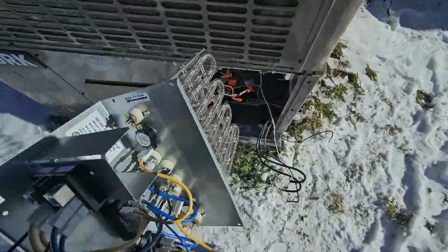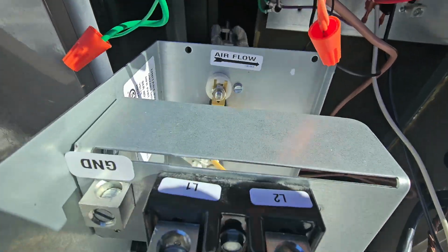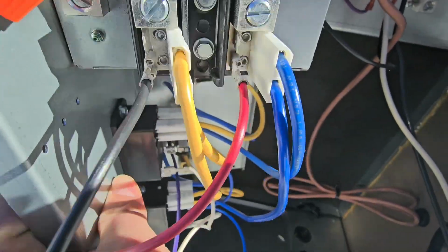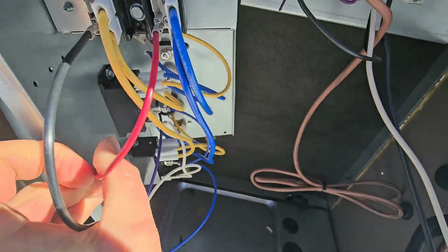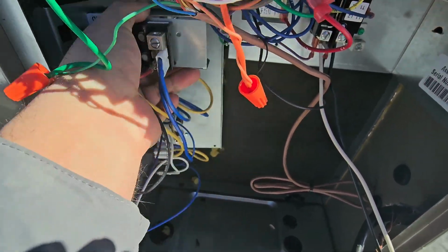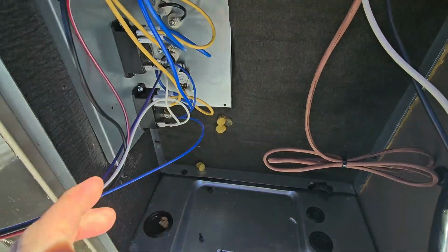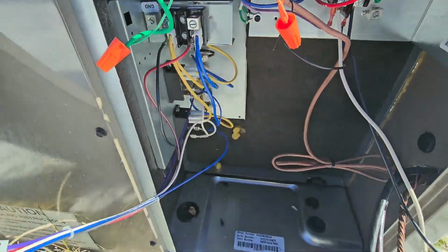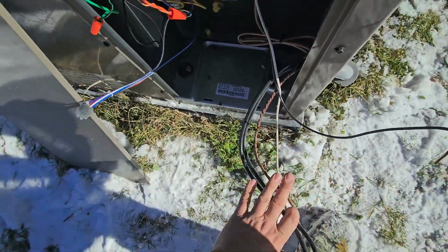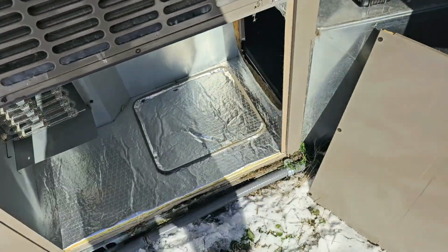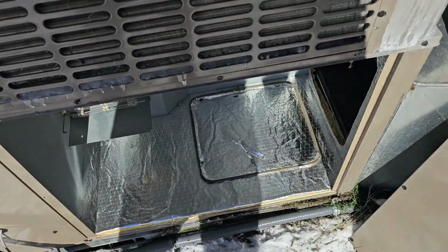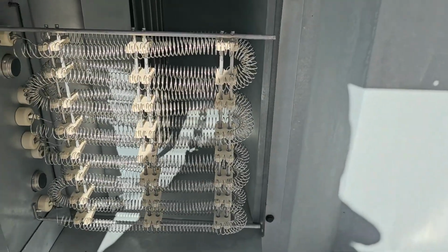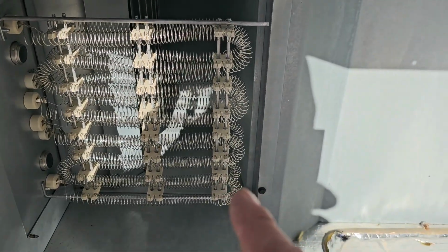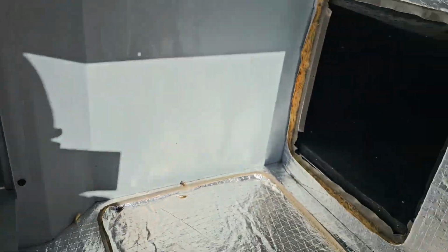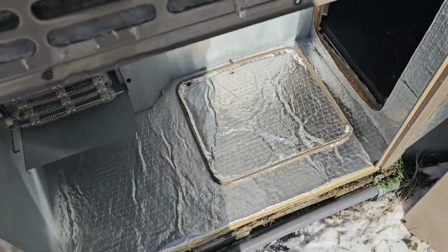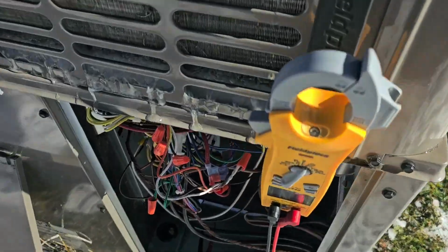Back on site, new heater kit going in. It's got four screws, so it's really easy to install though. See, and you just put the four screws in, two on top, two on bottom, and then wire it up. All right, we're ready. I got the panel off the supply side of the package heat pump so you can see the heater kit. There's the heater kit right there, right in front of the blower wheel, and there's the supply duct. So let's go back around here.